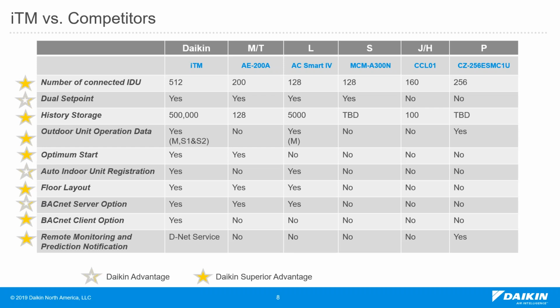If you look at optimal start, I think I gave it a yellow star or golden star. So Daikin is above the competitor in this. Maybe Mitsubishi is close. Auto indoor unit registration, I think we also have an advantage in this. Floor layout, Mitsubishi and LG can do the same thing, but floor layout could be used in the Daikin system as a graphical user interface when you use the BACnet client. So that's why I think this is a very good advantage, and we use that very, very well in different projects.